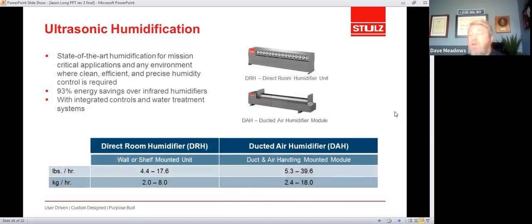Touch real quick on our ultrasonic humidification product. This is very popular in data centers and computer rooms because of the very precise control provided by the ultrasonic humidification. And not only that, because it is an adiabatic humidification process, we are able to provide some additional cooling to take some of the cooling off the HVAC equipment. These units are only using about 7% of the energy of say an infrared humidifier, and less than 40% of what you would expect in a steam canister humidifier.